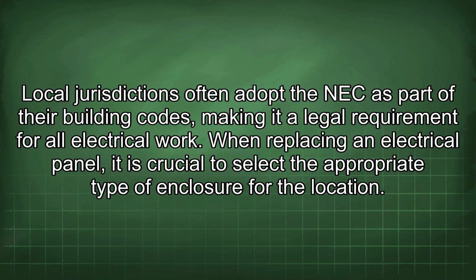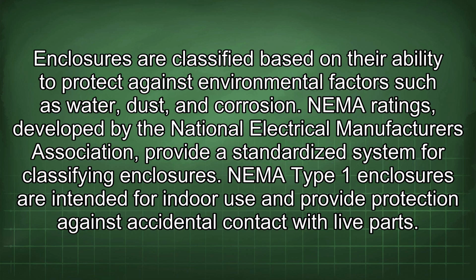Local jurisdictions often adopt the NEC as part of their building codes, making it a legal requirement for all electrical work. When replacing an electrical panel, it is crucial to select the appropriate type of enclosure for the location. Enclosures are classified based on their ability to protect against environmental factors such as water, dust, and corrosion. NEMA ratings, developed by the National Electrical Manufacturers Association, provide a standardized system for classifying enclosures.